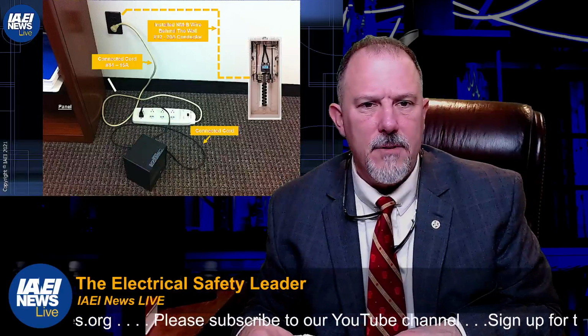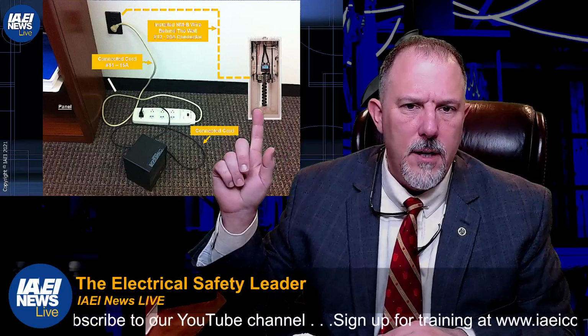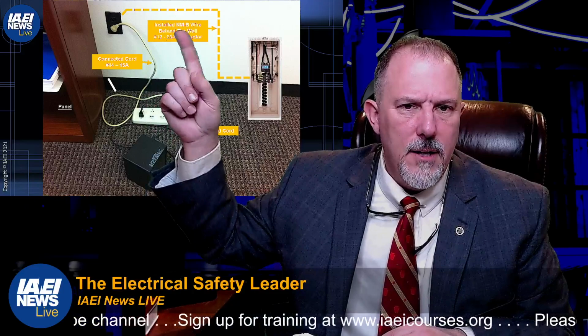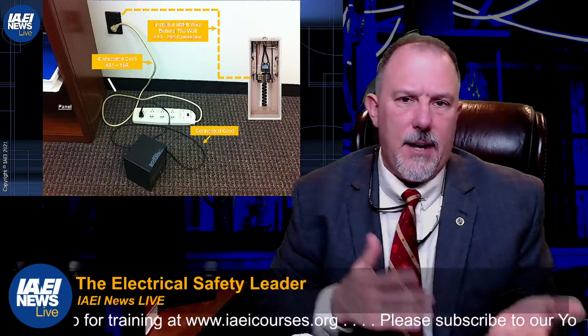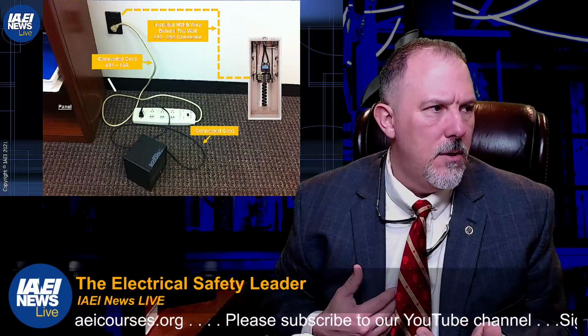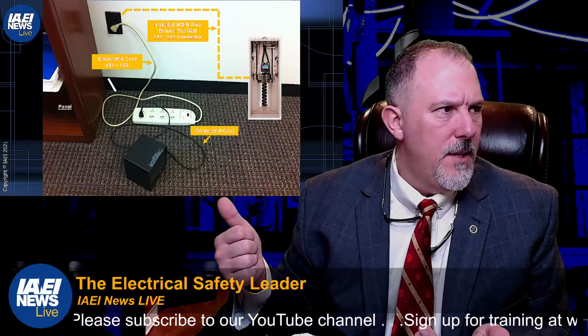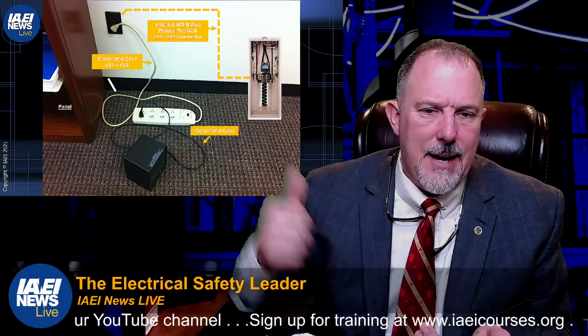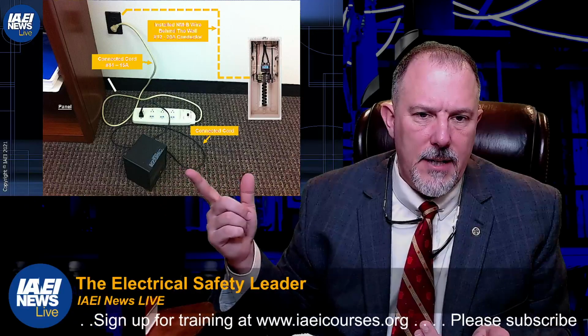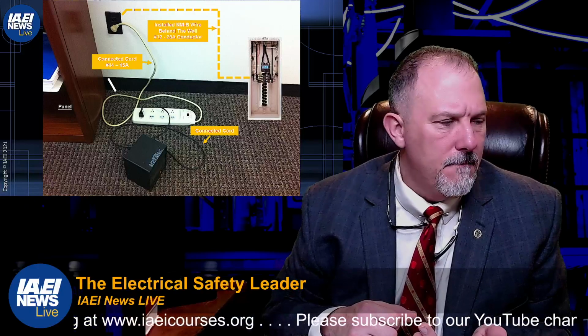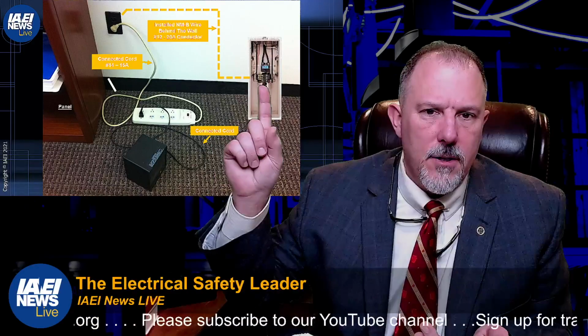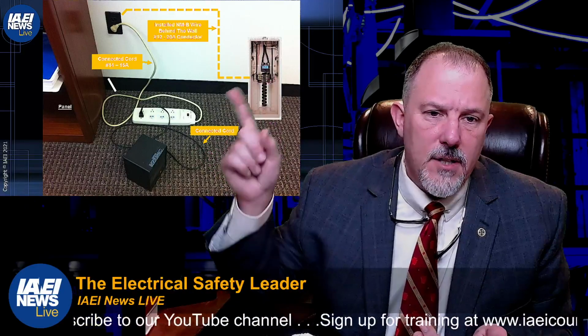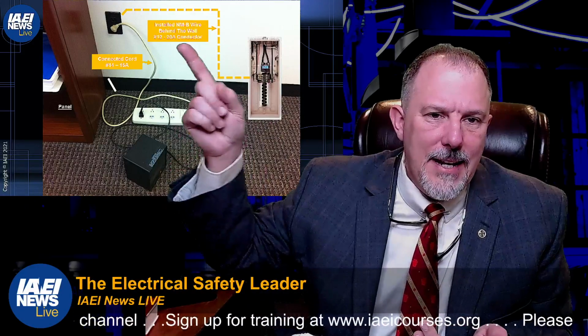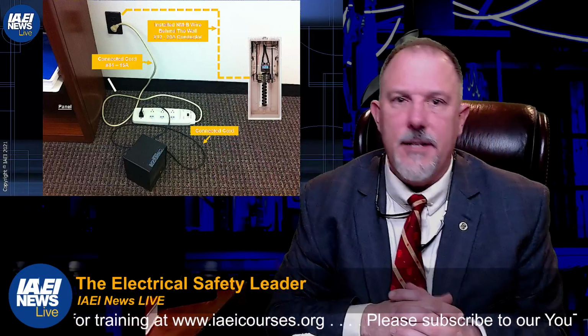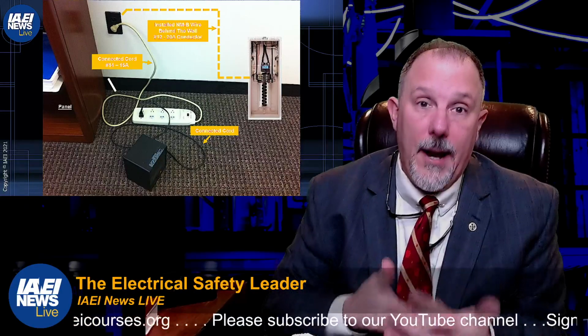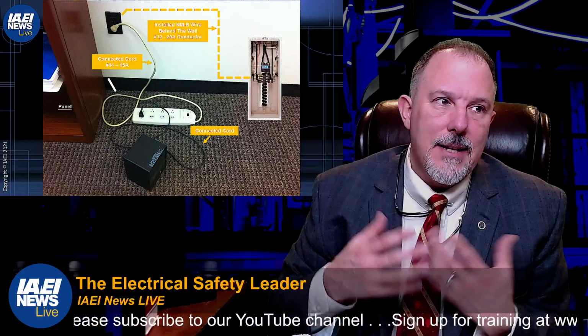Right? So if I think about this type of an installation, I have a panel board. I have a branch circuit that goes to a receptacle outlet over here. That circuit breaker protects the branch circuit that goes to that receptacle. It doesn't protect what's on this side of the receptacle. And in this picture, I've got a number 14, 15 amp conductor that goes to this multi-tap outlet. There is a connected cord to this heater element here. This is an SPT-2 two-conductor cord. That circuit breaker is not protecting that conductor. That circuit breaker is not providing protection for that heater. If that was a lighting outlet and there was a lighting fixture, that circuit breaker would be protecting the conductors going to that lighting fixture, that lighting luminaire or the lighting outlet, but it's not protecting the light itself.